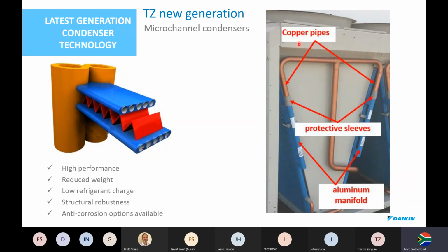However, importantly, I've included in the slide, you'll notice there's copper joining aluminium here. In the real world, you can't do that. You can, but it's not going to last very long, because in the event of this getting wet, this whole coil becomes a battery. And when it becomes a battery, this coil will generate probably 4.5 to 5 volts when it gets water on it. And as such, the aluminium coil will start forming a powder, and it will become what you call a self-sacrificial anode. We don't want that to happen.